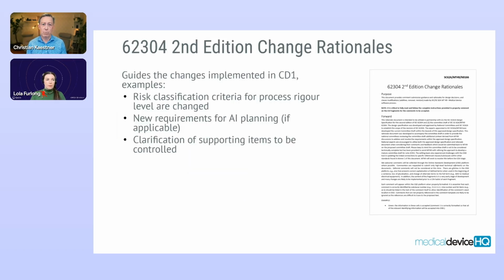Together with the CD, a change rationale was provided to explain the changes being made. I've selected a few key topics addressed in the document, and I will also revisit several of them shortly and explain them in more depth. The classification will be called process rigor level, and the criteria for the determination will change. And the reason for that is that basically, as I said before, it is a process standard, and what you determine is the rigor of the process you shall apply when developing software. In the past, software safety classification has been misunderstood as determining how safe your software becomes. And that's not the point. It's more about determining the rigor of the process you apply. New requirements for AI planning will be part of the second edition.